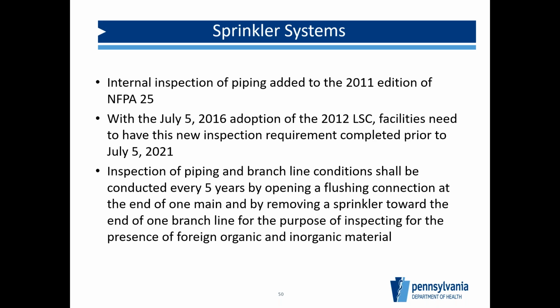It's one of those things where I wouldn't recommend everybody going out in June of 2021. And I'm sure I'm not the only one who can't believe it's already 2020. So 2021 will be right around the corner. But what you want to have done is the internal inspection of your piping and branch line conditions, conducted every 5 years, and they have to open a flushing connection at the end of one main and move a sprinkler toward the end of one branch line to do this inspection.